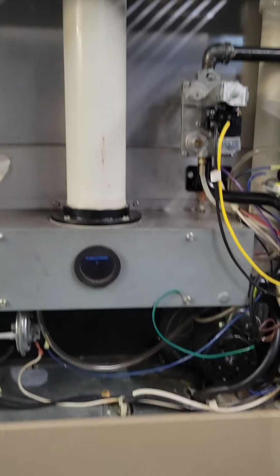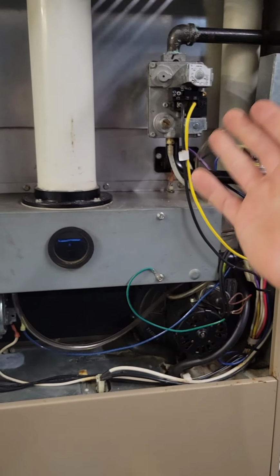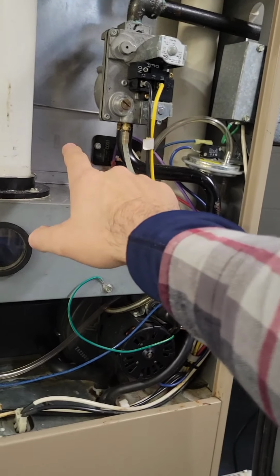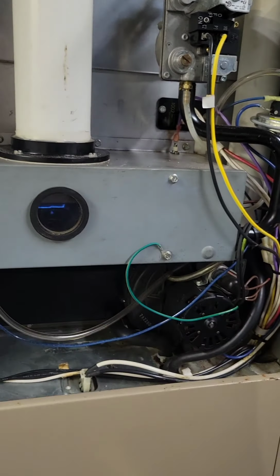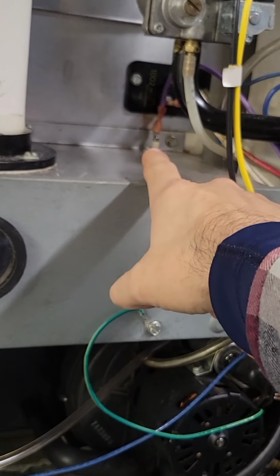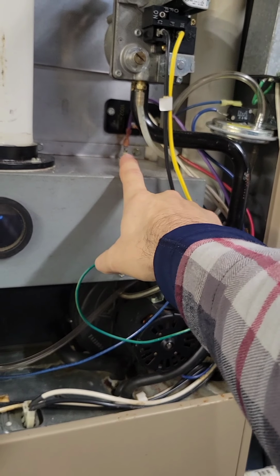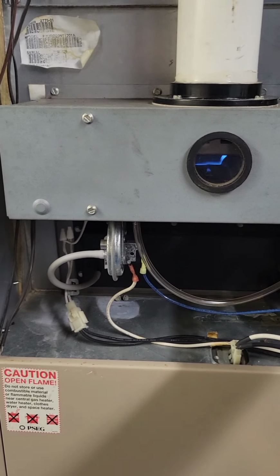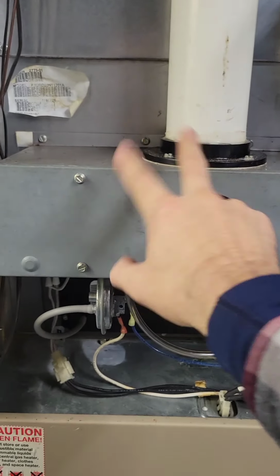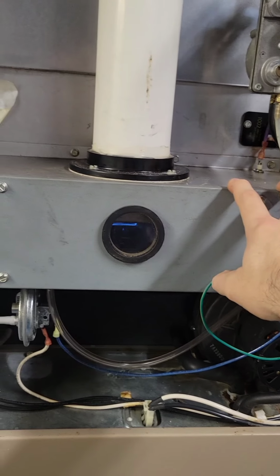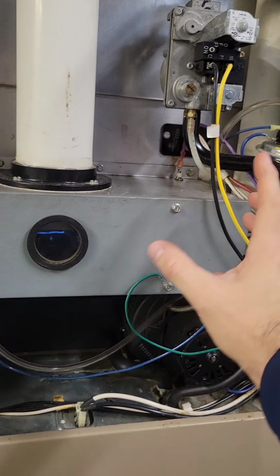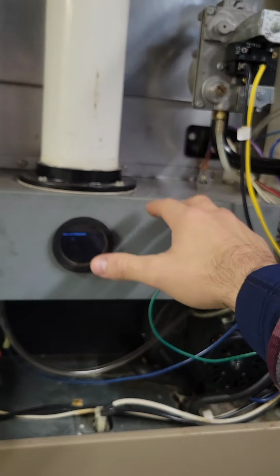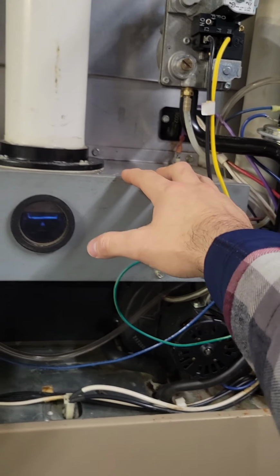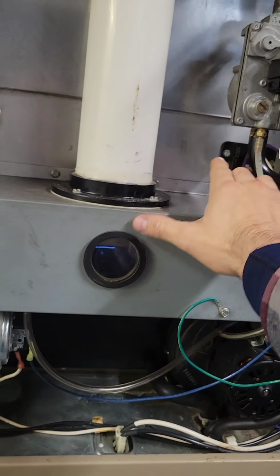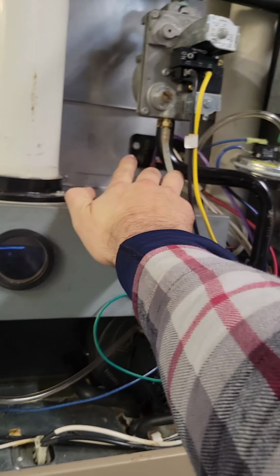But yeah, that's kind of what I like to do on the maintenance, is make sure all your safeties work. You have your high limit switch back there. Some furnaces are different. This guy's a little bit older than most. But definitely clean the flame sensor, which is located actually on the right hand side on this one. Most of the time you'll find that the igniter is on the right hand side, and the flame rod is on the left hand side of the units. Some, however, would have it opposite. And again, that's because depending on where the gas valve starts, that's where you have your igniter from, because that'll be the first burner it kind of hits. Obviously in this case, it's a little bit different. But that's the high limit sensor back there.